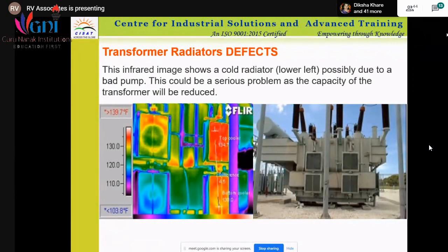So here we use thermography, and it is nothing but a simple camera like we use in photography, but it is supported with software, and it will give the indication of which part is used, or where the temperature is raised. One drawback is there: it only gives you the indication of where the problem is, but it will not tell you why the fault is there. That fault identification has to be understood by yourself, that is called judging. Like there are three terminals for three phases, and only one phase is getting heated. It will show you only the phase which has been heated, but it will not give you any indication why it has been heated, and that is to be analyzed by yourself. This is called thermography.